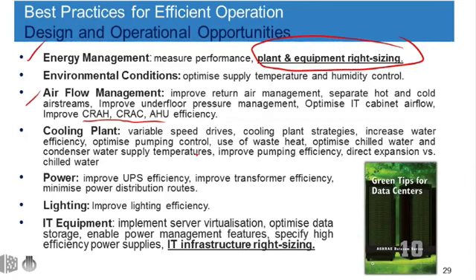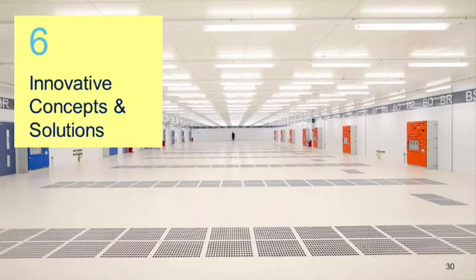Power, UPS efficiency. There's been some great strides over recent years with UPS, and in fact, with the improvements made with the mechanical engineering systems, the focus has really gone back onto the electrical side of things, and transformerless UPS is certainly helping in that respect. Then there's the more miscellaneous systems such as lighting. Now, although that's a fraction of the load within the data center, there are other upsides to energy efficient lighting. If you think about LED, for example, there are other advantages, not just about the energy efficiency, but in terms of the hours of operation compared to other types of lighting system, and therefore the less frequent need to go into the data hall in the first instance.